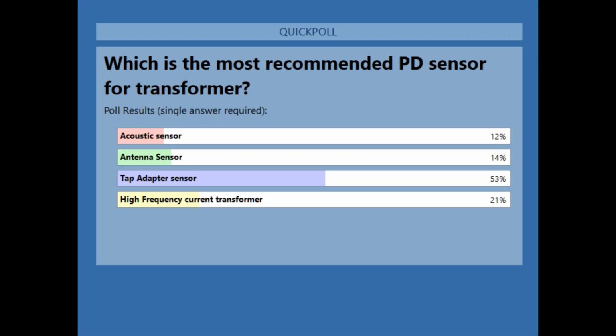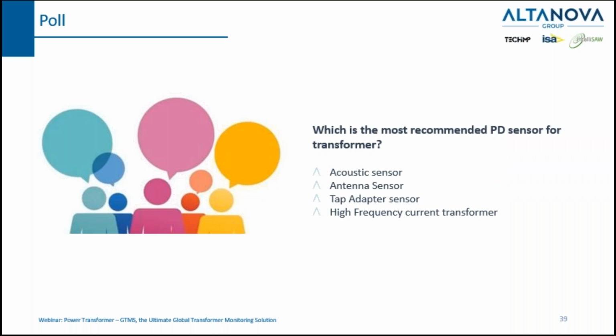The right one is the tap adapter sensor. So more than 50% of you responded correctly. Then 20% chose the high frequency current transformer, HFCT, then the antenna sensor and the acoustic sensor. As I said, we prefer to use the capacitive tap, the tap adapter, even though it is possible to run this test and configure the monitoring system using other types of sensors, like antenna, acoustic, or CT, according to the layout and the possibilities.